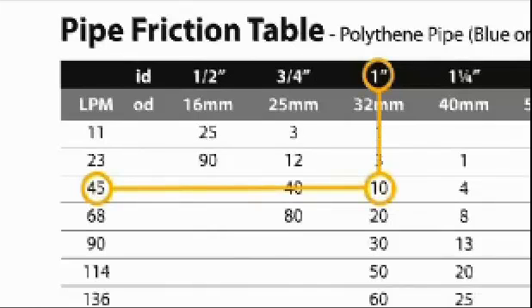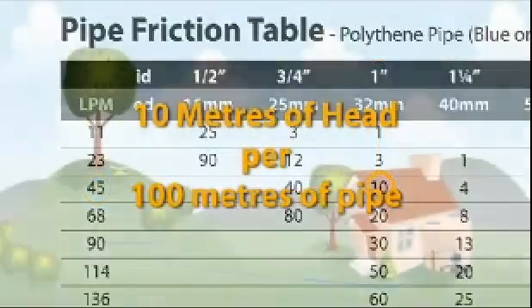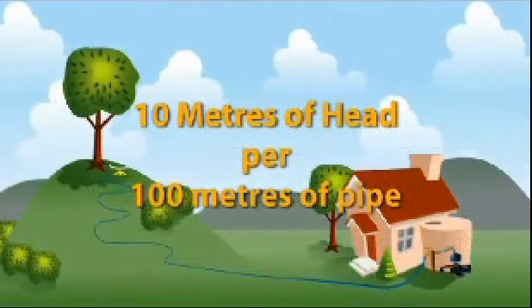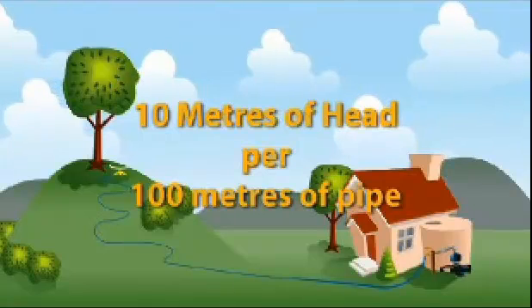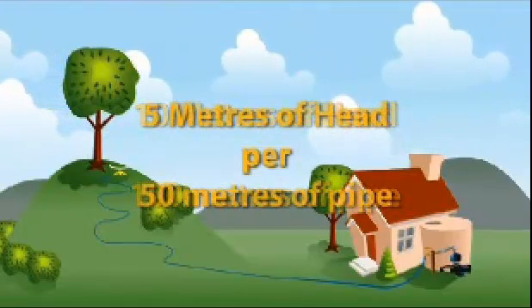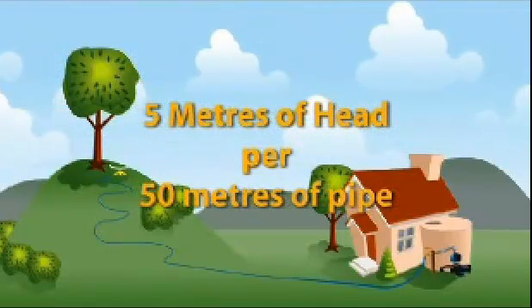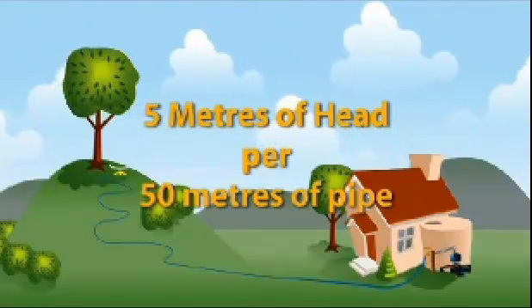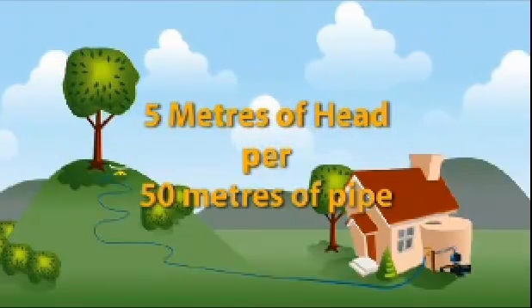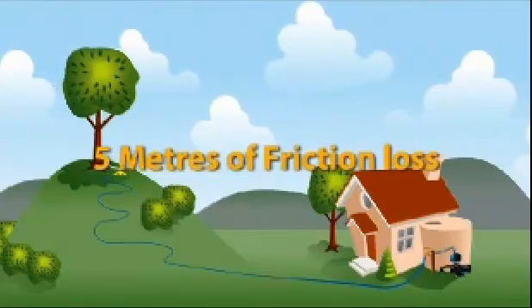We can see that there will be 10 metres of pressure lost to friction. However, as we know, in this chart, all values apply to 100 metres of pipe. In Aunty Flo's case, she only requires 50 metres of pipe. Therefore, we must halve the value. Half of 10 is 5. 5 metres is therefore our friction loss.